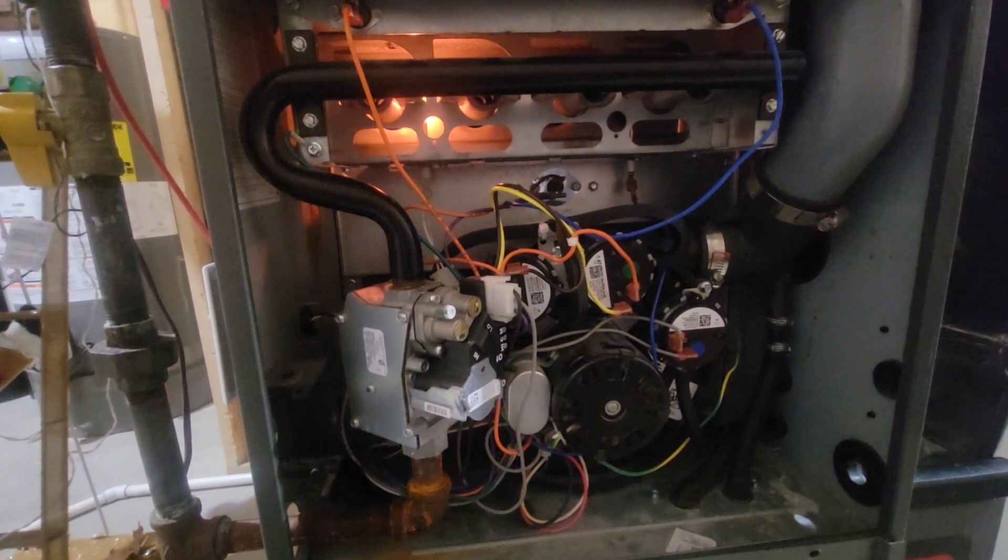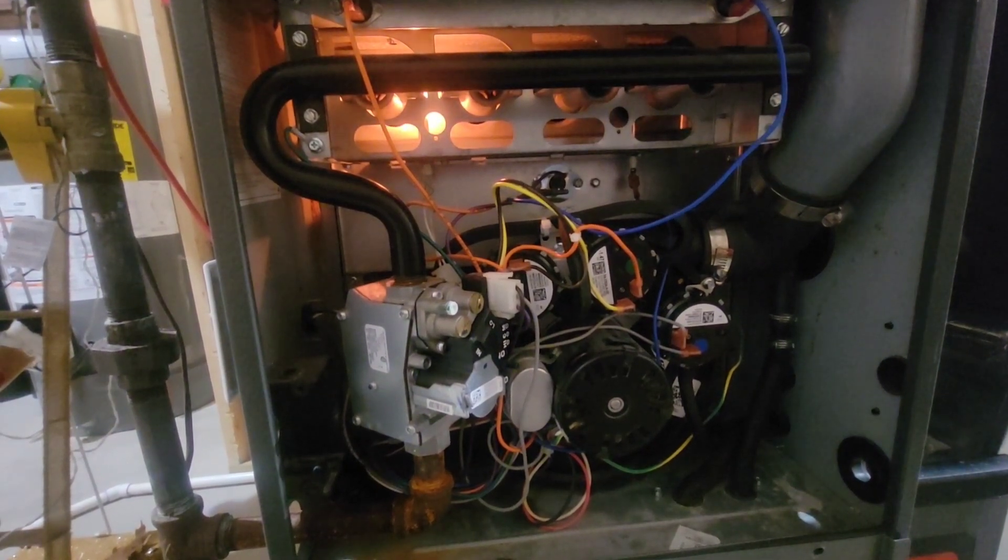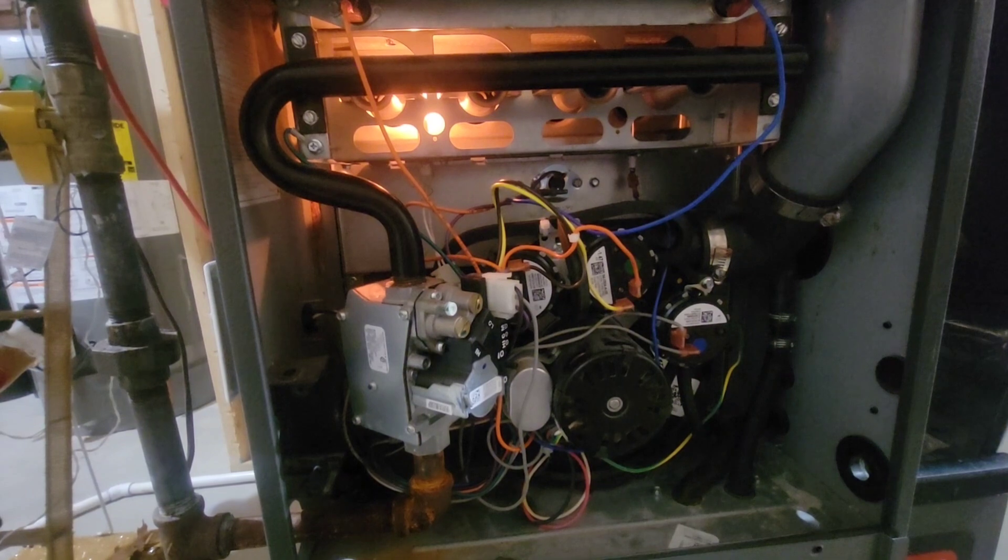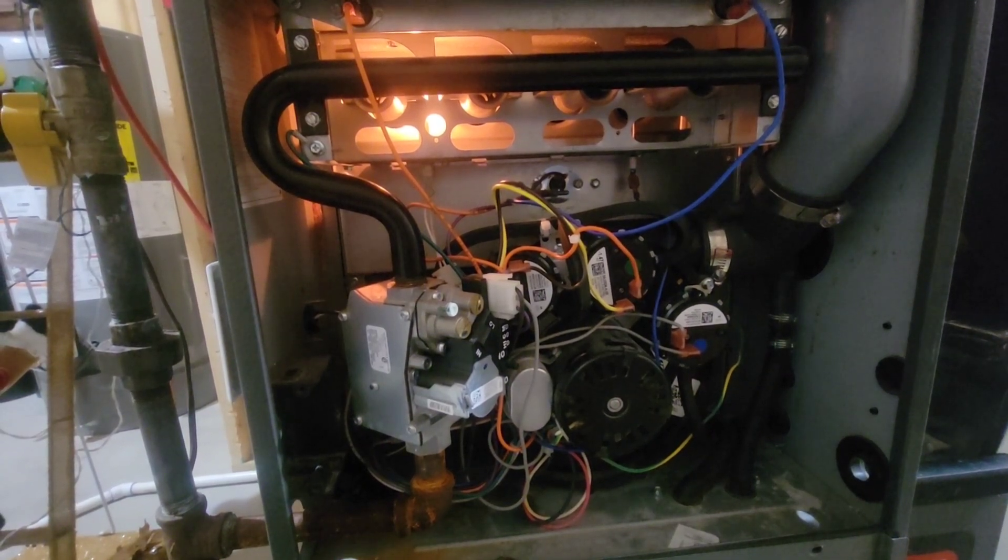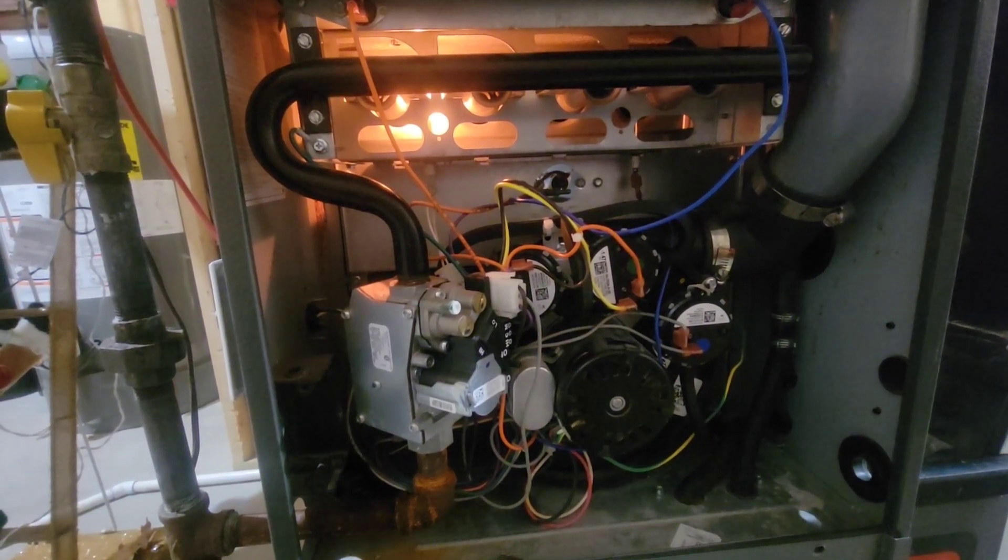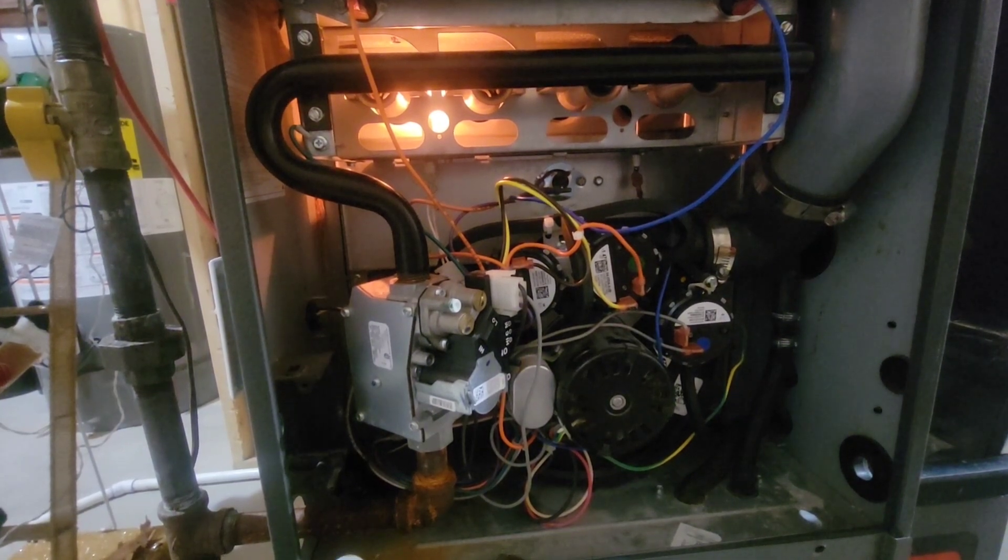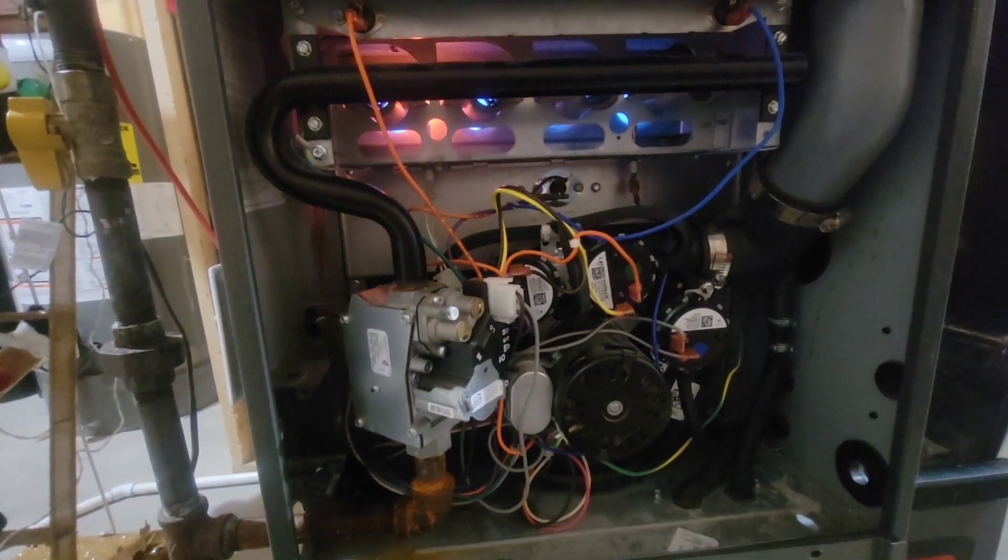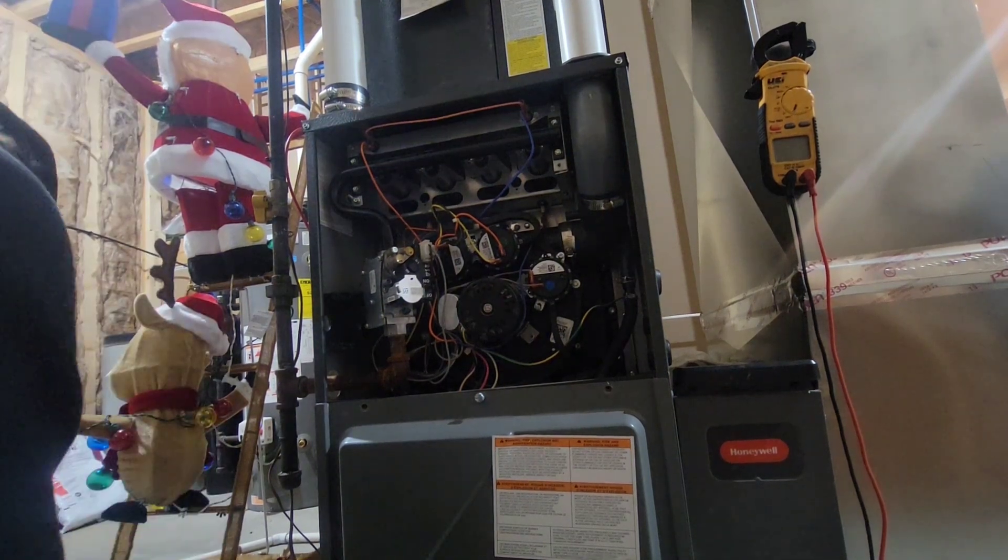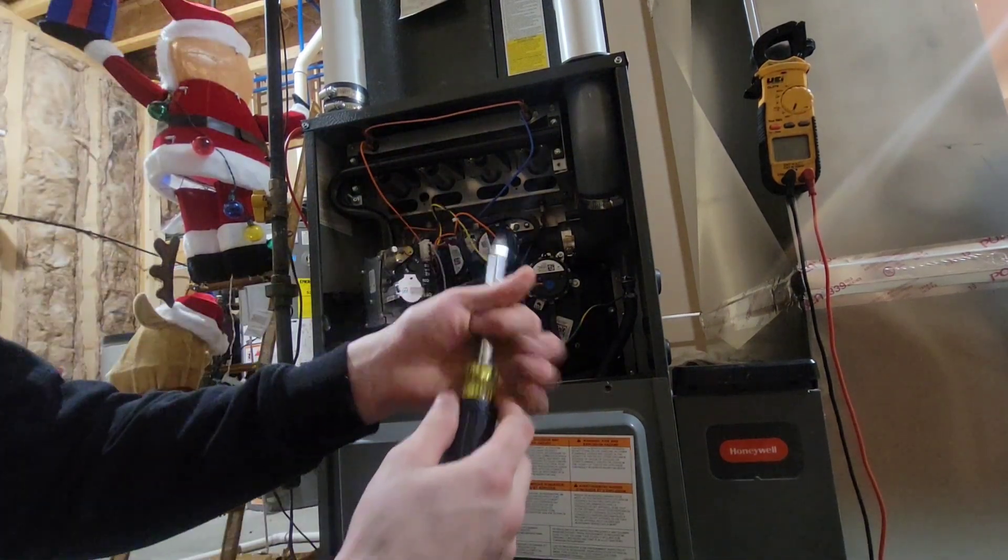We've got our ignition, so our pressure switches are making. We will not have that igniter powered up if those pressure switches are not closing properly. We should have gas valve here shortly. There's flame, there's gas. They're all looking good. We're definitely pulling out good exhaust. We're going to go ahead and throw the door back on here.